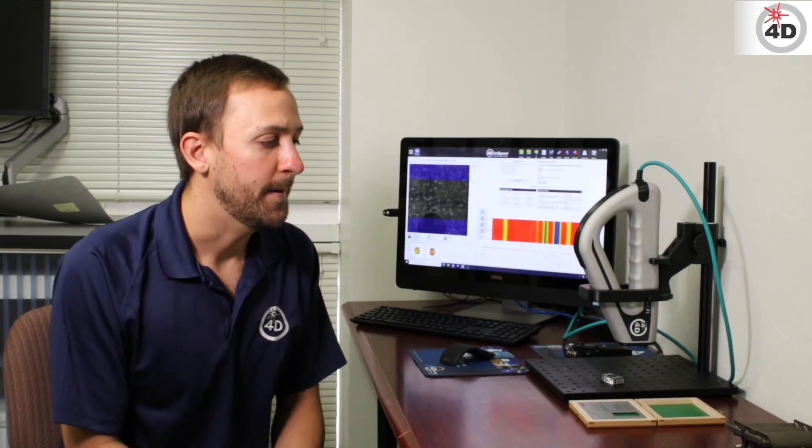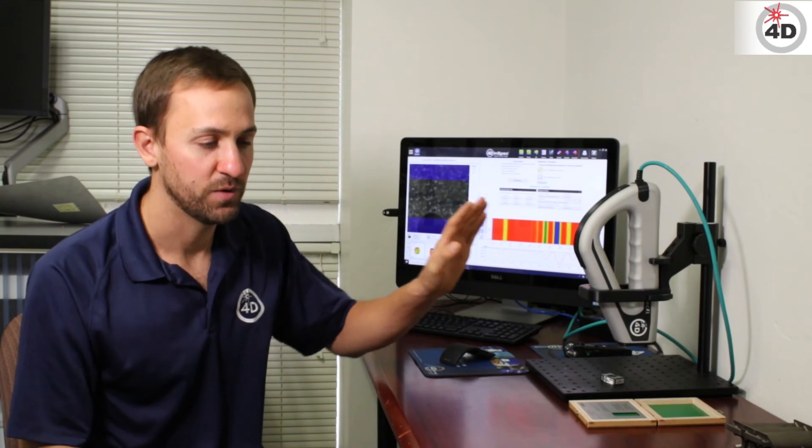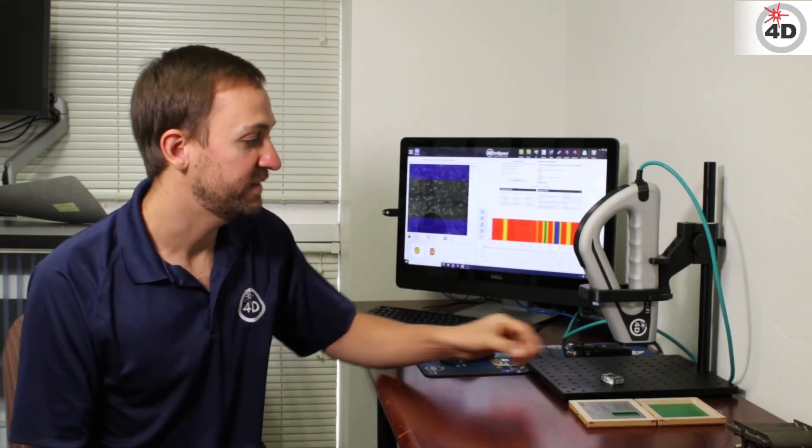The reason being is that the instrument doesn't really go out of calibration unless it's broken. There's no moving parts in the system. And if it's broken, let's say you drop it on the stairs or whatever, it won't even give you data. So if the instrument is misaligned, there's no data given to you. So you either get data that's in calibration or no data at all.